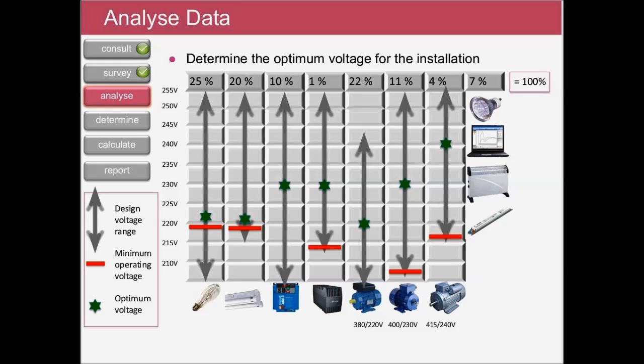Again, it's really important to ascertain the proportion of energy that's consumed by the voltage-dependent loads. The savings associated with these loads is of course going to vary from item to item, and understanding how each load will react to a voltage reduction is really the key to assessing the overall viability of the selected offering. Then if a reasonable energy saving opportunity is evident, a more detailed analysis may be required to ensure that the installation is not going to be negatively impacted through the introduction of that equipment.